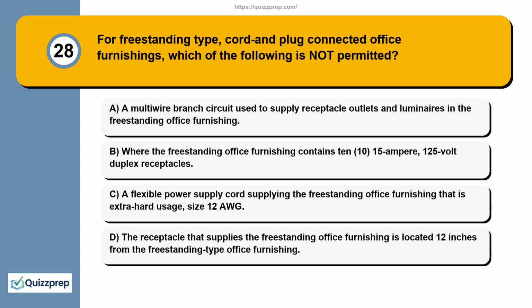Question 28. For freestanding type, cord and plug connected office furnishings, which of the following is not permitted? A multi-wire branch circuit used to supply receptacle outlets and luminaires in the freestanding office furnishing, where the freestanding office furnishing contains ten 15 ampere, 125 volt duplex receptacles. A flexible power supply cord supplying the freestanding office furnishing that is extra hard usage, size 12 AWG. The receptacle that supplies the freestanding office furnishing is located 12 inches from the freestanding type office furnishing.